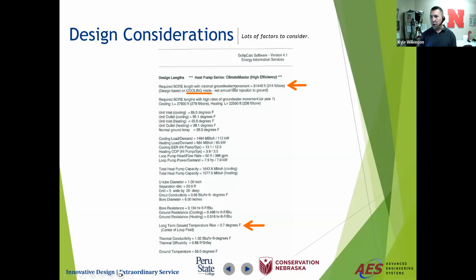With minimal groundwater movement, this was a 5 by 20 grid, and it told us we'd need 314 feet per bore. That starts 5 feet down, since the top 5 feet isn't used, as the piping runs horizontally back to the building roughly 4 to 5 feet underground. You can see all the parameters here.